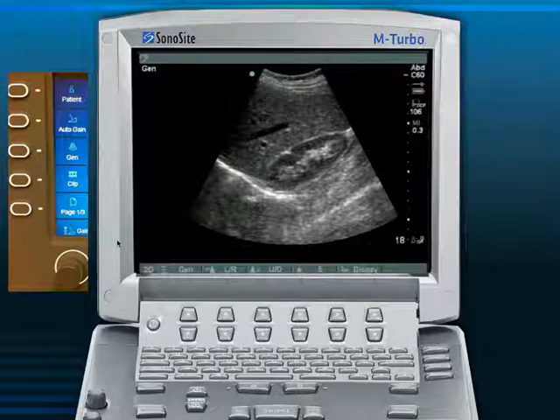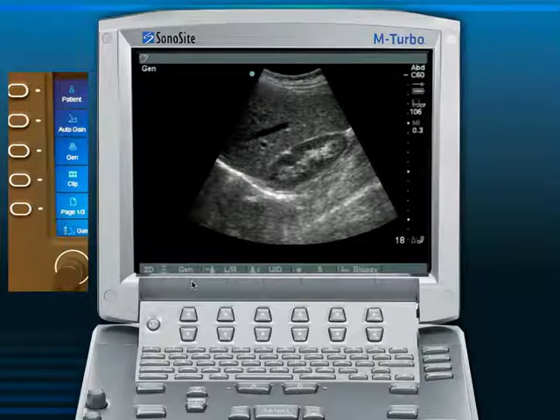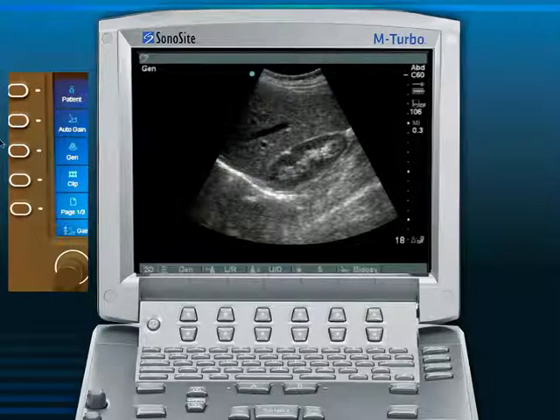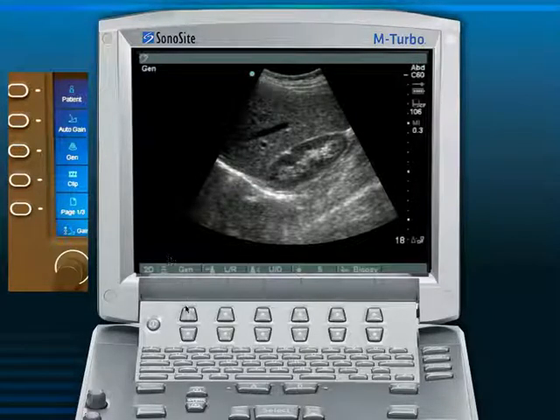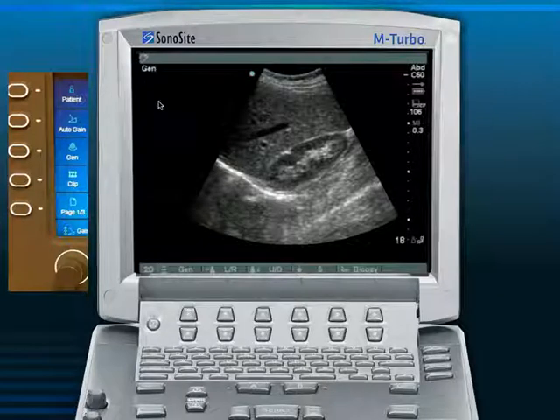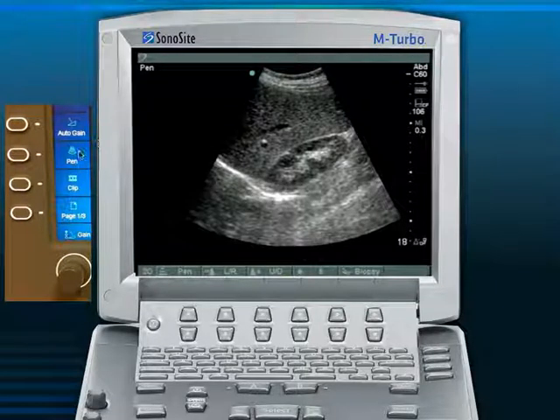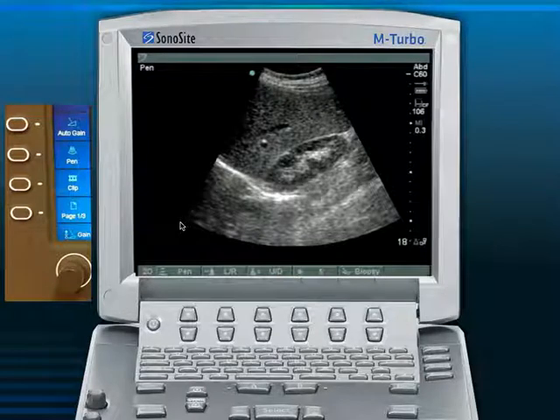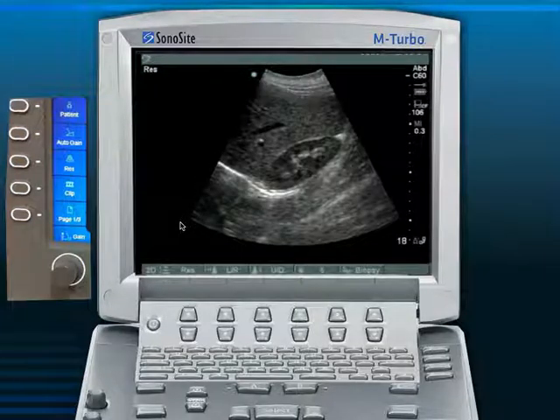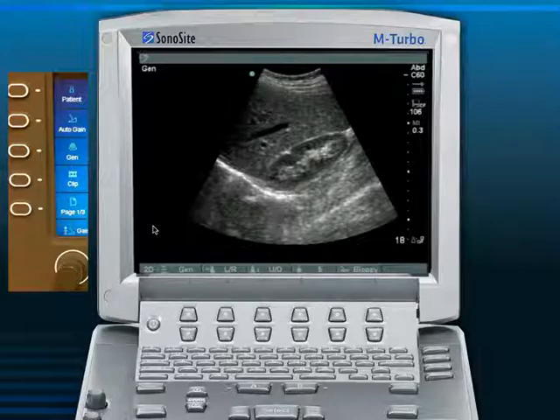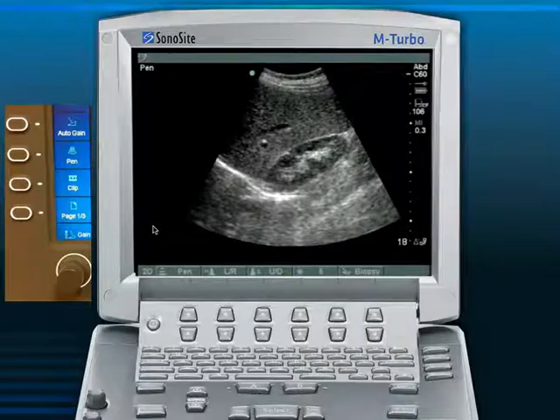To change the frequency, there's a button on each machine that toggles through modes. Pushing it cycles from gen (general), which is the middle frequency range, up to res (resolution mode) — the highest possible frequency — and then down to pen (penetration mode), the lowest frequency for large or obese patients. For example, if the range is one to five megahertz: gen is three megahertz, res is five megahertz, and pen is one megahertz.